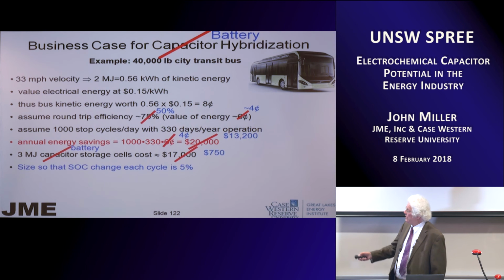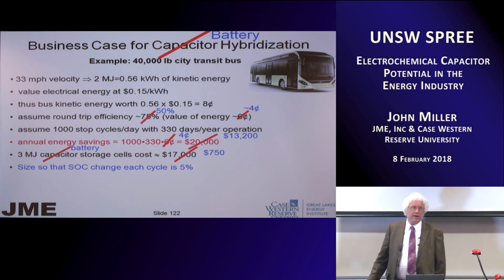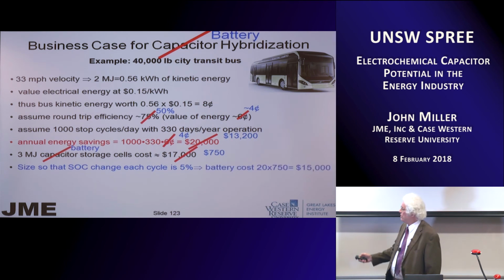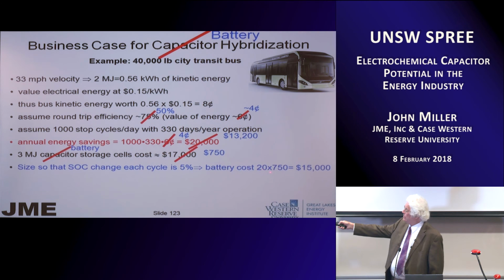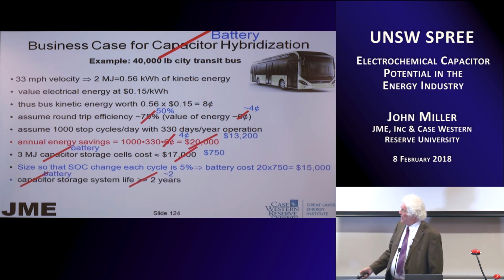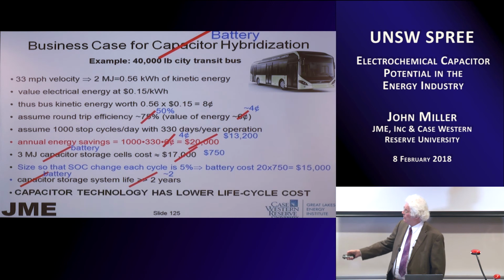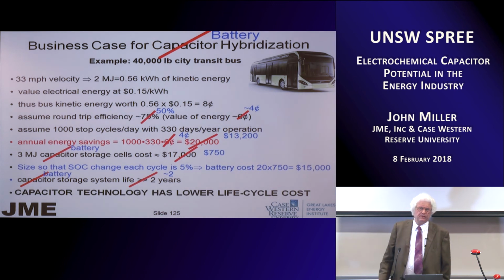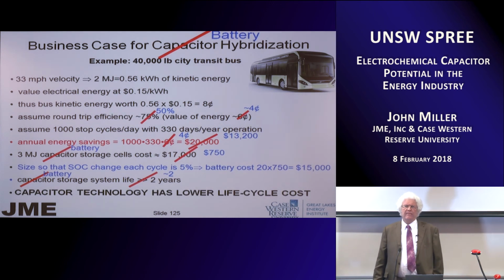However, one must have a limit on the charge rate of the battery system, so they can only change it by 5% state of charge, so we have to have a 20 times larger battery. We have to supersize the battery to make it work here, and that brings the price very comparable. The life is only about 2 years for the battery system, so the capacitor certainly offers advantages over the battery in this application.